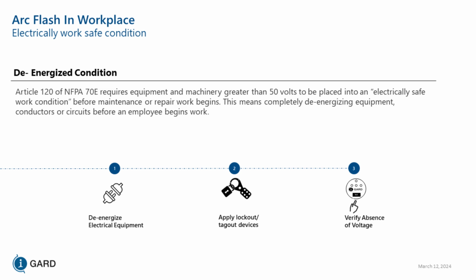So in both cases, we try to get into a de-energized condition. Article 120 of NFPA 70E and the corresponding article in Z462 requires electrical equipment and machinery greater than 50 volts to be placed into an electrical safe work condition. And they describe how to do it. So you have to de-energize the power conductors, any stored energy, and put measures in place to ensure that anyone working on that equipment is going to be safe from accidental contact with exposed conductors. This means completely de-energizing the equipment, conductors, or circuits before employees could begin to work.